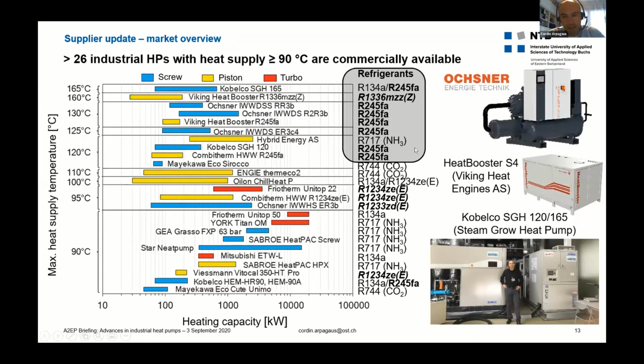Those are the examples. Then what is important are the refrigerants used in the heat pump cycles. They are listed here, and you can see that at 90 degrees and up to there, there are the ammonia heat pumps which can deliver that heat at large scale. Then we have also CO2 up to about 110 degrees. And then at higher temperatures, there is the R245FA, which is a hydrofluorocarbon, and it is facing phase down due to new regulations of refrigerants. So there is a need to replace these refrigerants here in the top temperatures.